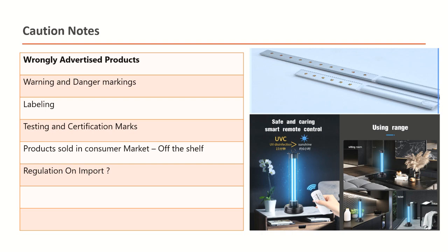And there is no such data available, because the UV dosage to inactivate surfaces by these wands is very difficult to determine. Or when you use these products, it may give a false impression that the area has been disinfected, where actually the disinfection is not proper or not full, or the level of disinfection is not there as required.